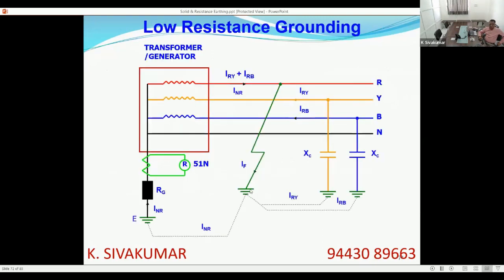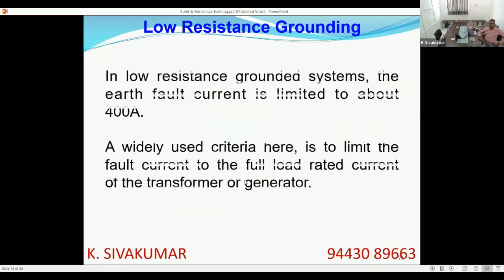Then low resistance grounding. In low resistance grounding, we are connecting a very low value resistor directly in the neutral to ground path. Here, since the current is significant, you can connect a neutral CT and connect a current operated relay also. In a low resistance grounded system, the earth fault current is limited to about 400 ampere.